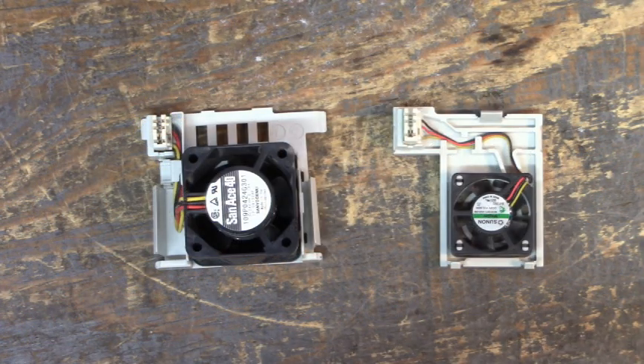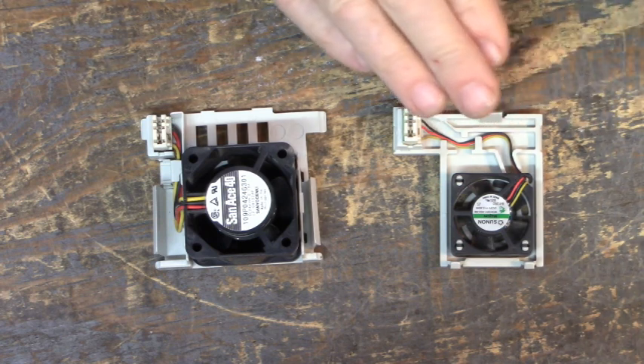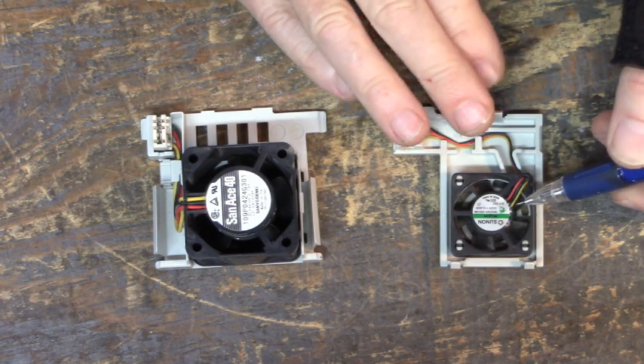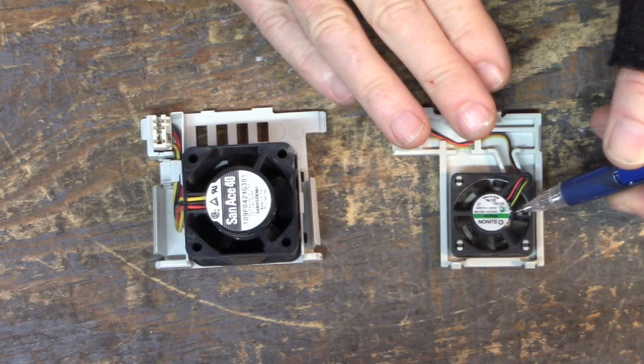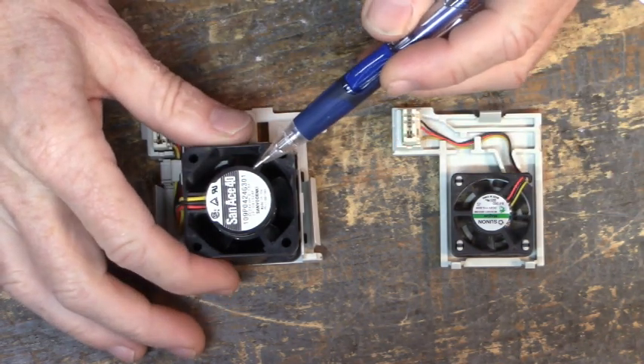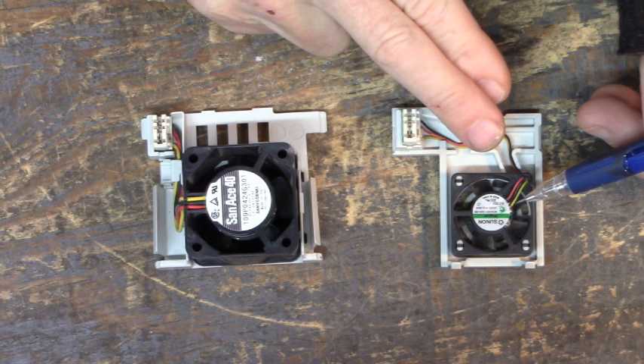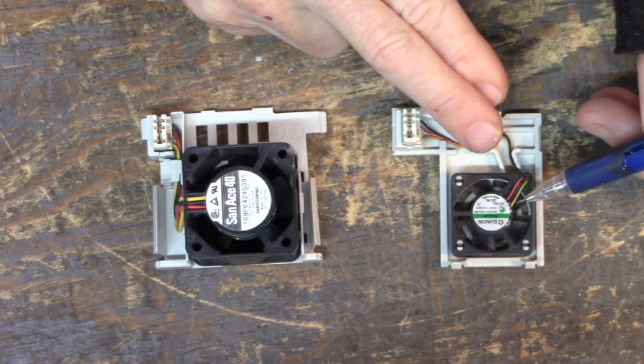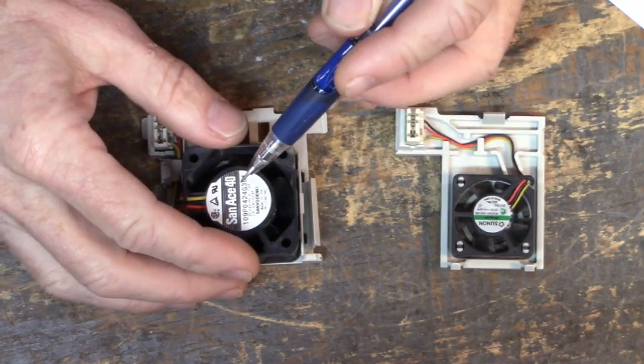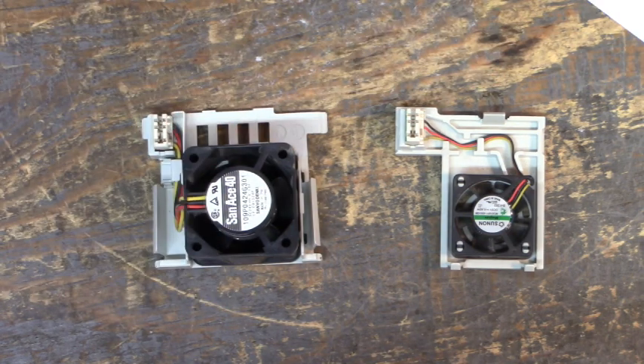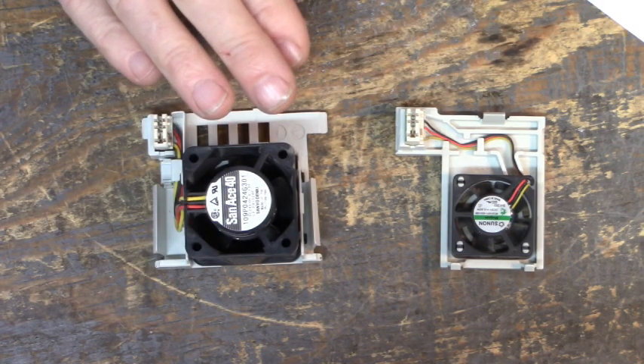Good morning all. Here are two cooling fans from a Lenze drive type E84AVTCE3024SXS. Now this smaller cooling fan here does not rotate. It's bad. It's going to have to get replaced. This larger one is good. This one here cools the control board. This one here cools the heat sink assembly that the IGBT and three-phase bridge sit on.